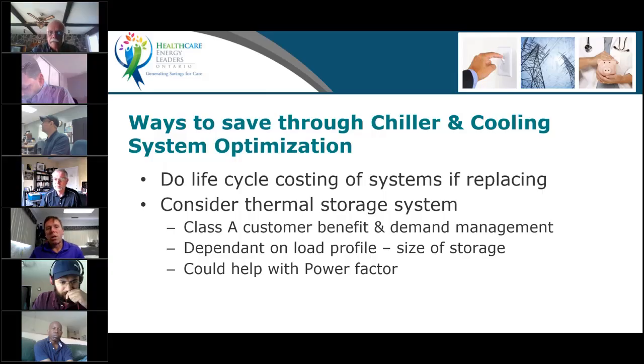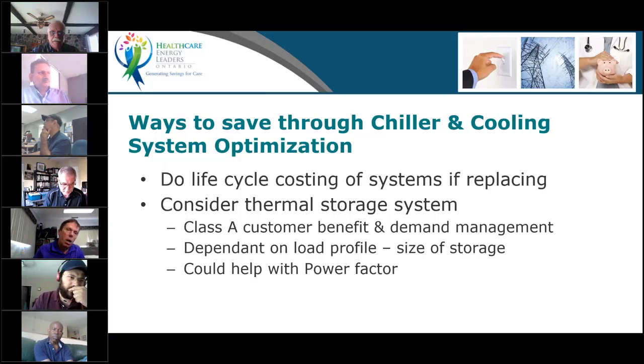The question I'm often asked: does thermal storage save energy? For heating purposes, it does not. If you put thermal storage for heating purposes, which we do in Quebec, it costs you kWh because there are losses from the storage. In cooling, it may save you because it can allow your chiller to run at a better efficiency, and also you can run them off peak. So it can save you both energy, but most likely cost, not only because you can avoid GA hours, but also, if you're on the hourly Ontario energy price, you can run at times when electricity is cheaper and then empty your storage during the high-cost daytime hours.